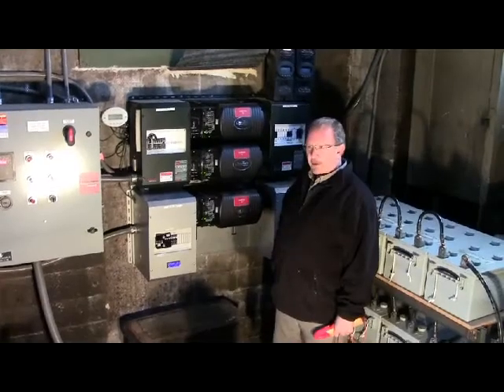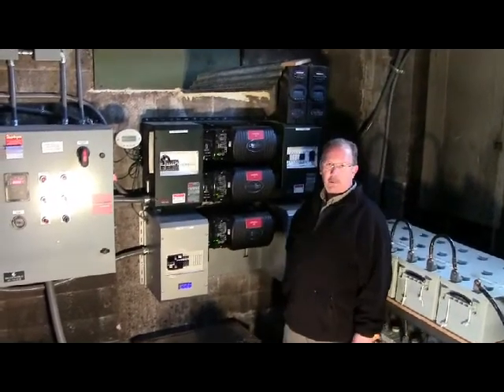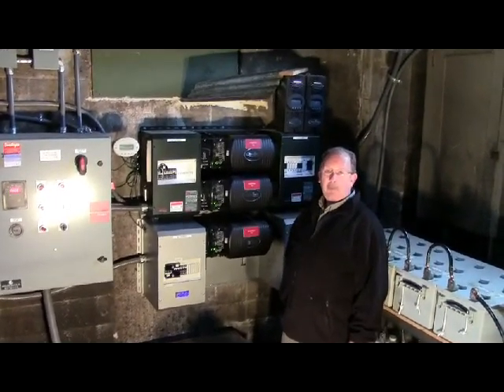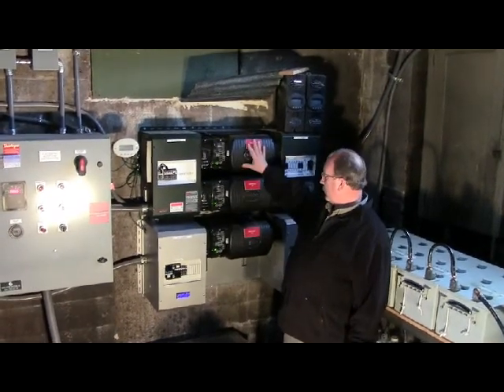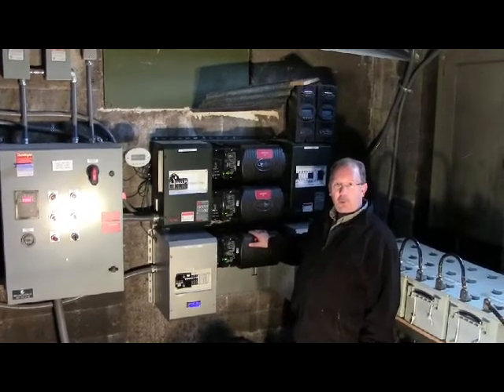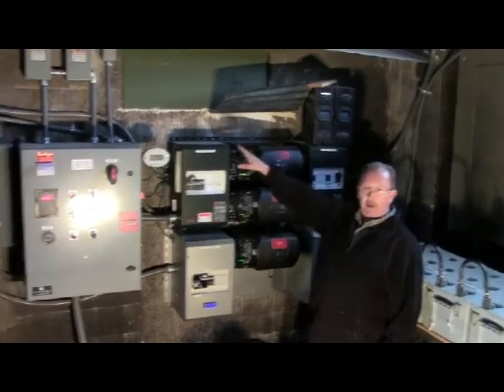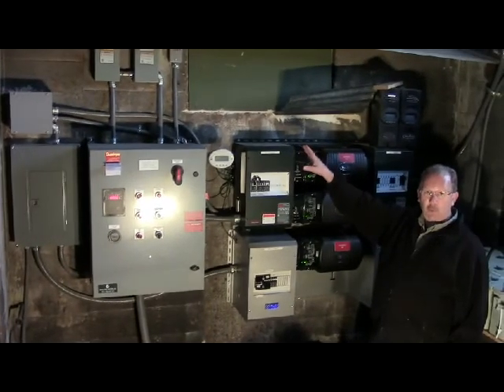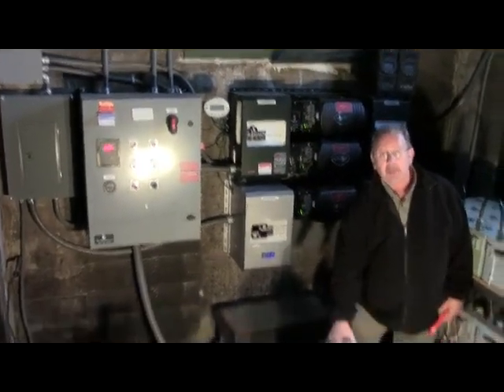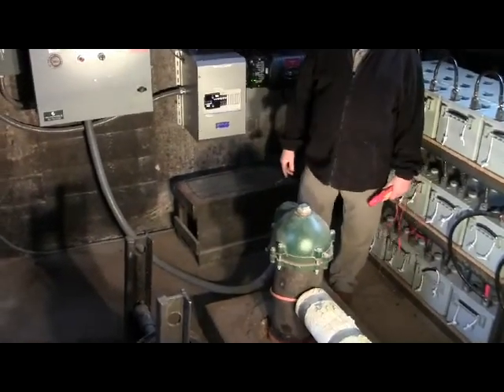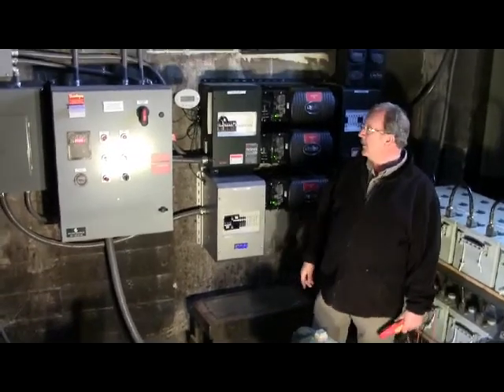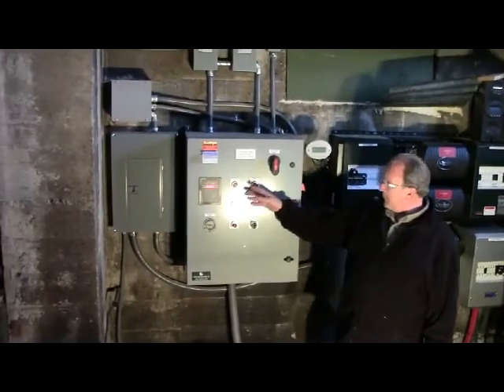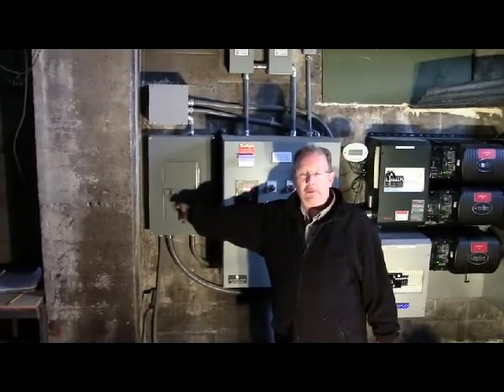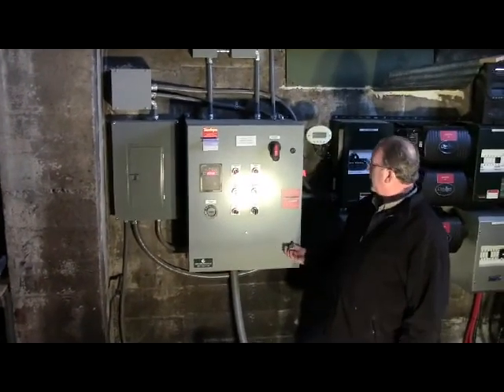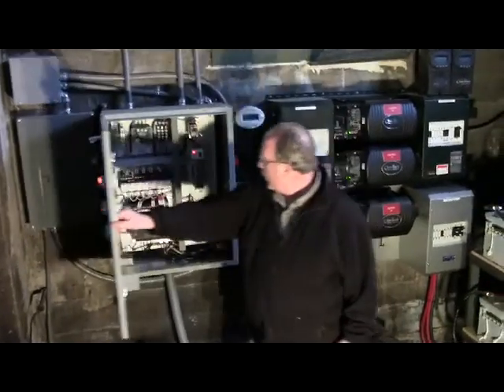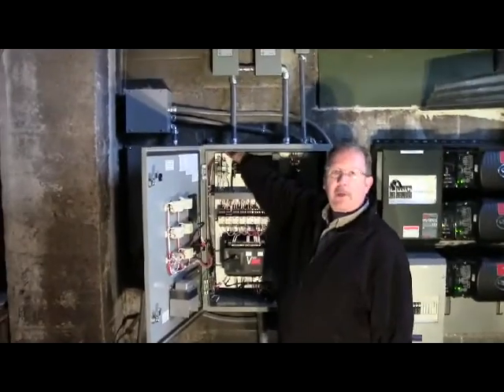Okay, this is an application where we would use buck-boost transformers to boost our voltage from 208 up to 230 volts. I have here inverters, there's 3 of them, and they can only produce 208 volts. We have a generator in another building that produces 208 volts as well, but our pump right here, which is 600 feet down the ground, has to have 230 volts three-phase. So what I've done is I've come from my 208 volt panel and I have brought the wiring from that 208 volt panel up through here.